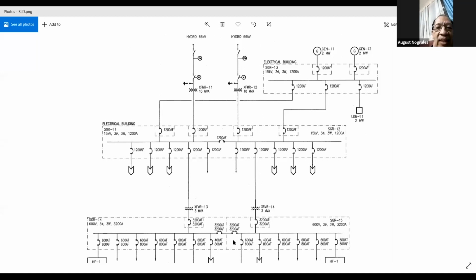Okay, let me pull that up here again. The question goes like, what is the advantage of having a double tiebreaker? So I think you're referring to, say, the difference between the tie between switchgear 11 and 12 and the double tie between switchgear 14 and 15. Yes. So I'm not aware of any particular advantage other than just redundancy in the system. It may depend on the particular interlock design of the system as well. It may also depend on the specific vendor equipment that was used here. I can't recall the specific model or vendor switchgear that was used in this application, but if the standard equipment comes with a default tiebreaker at one end of the bus, then maybe you end up with two of them.